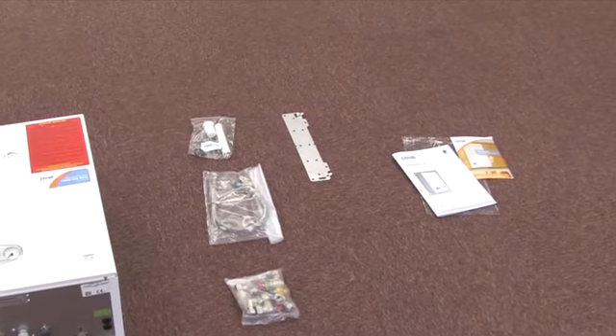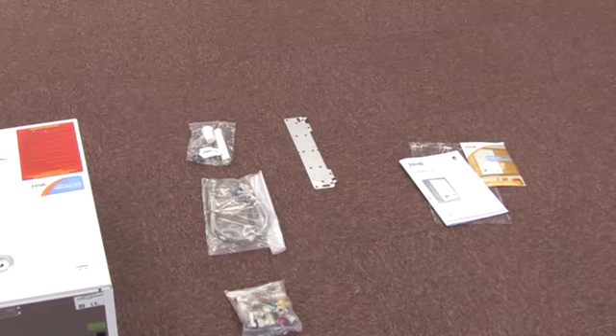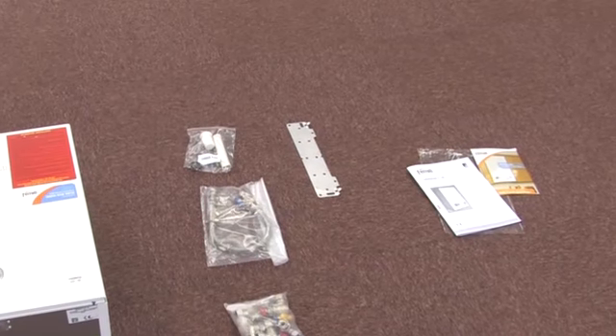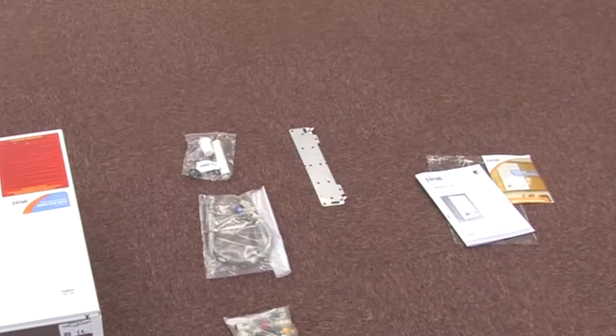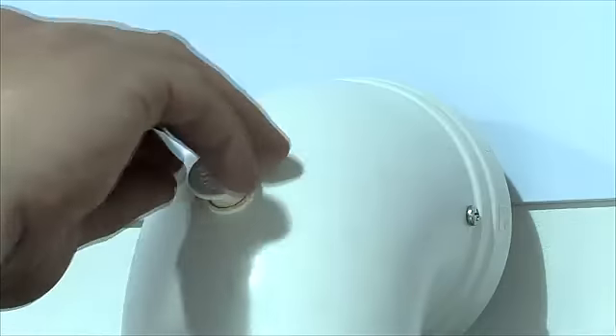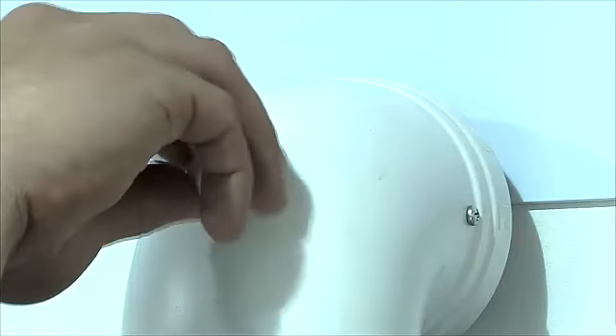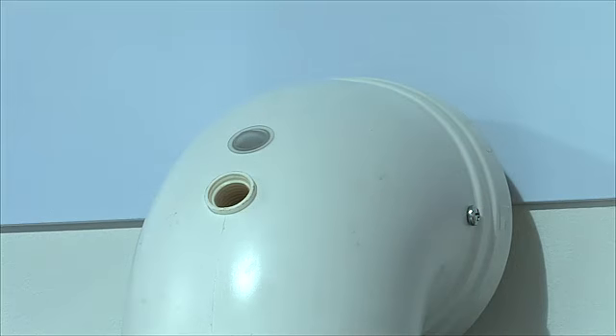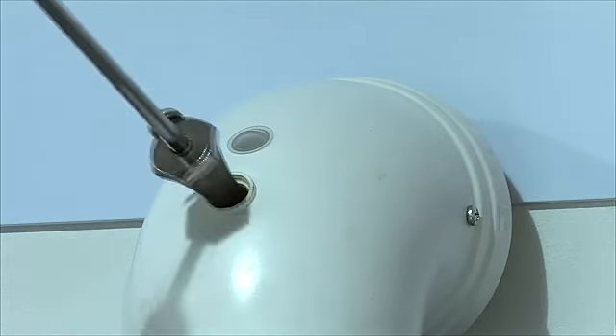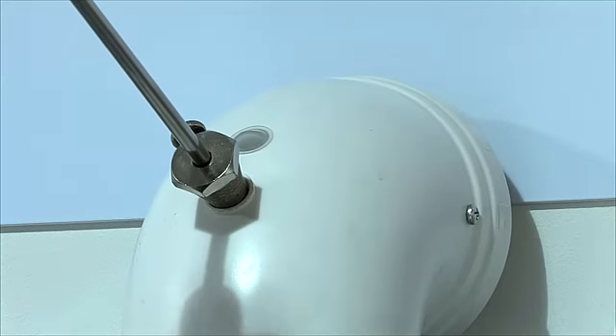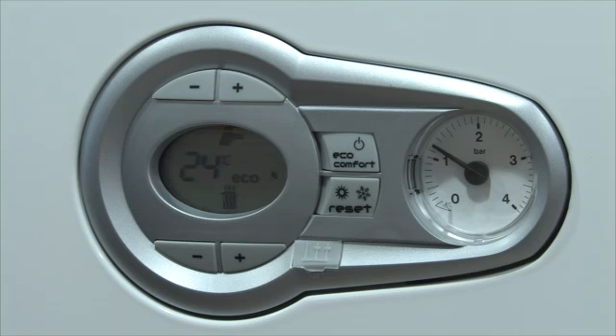Being light enough to need only 1 pair of hands, attaching the Modena to the wall hanging bracket is easy and straightforward. Commissioning the Modena is a quick and simple process. Ensure that the appliance has been firing for several minutes, remove the flue test point, and insert an analyzer probe. The electronic module can be used to put the boiler into service test mode.